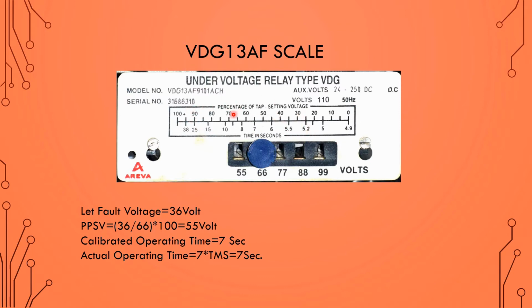And if you see the table, earlier in the case of over voltage it was PSM versus trip time, or PSM versus calibrated operating time, but here it is the percentage of tap setting voltage, or the percentage of this plug setting. So that means how much percentage of the plug setting you are giving, this shows that. 100% you are giving, 90% giving, 80% giving, 70% giving, or 0% giving, means 0 volt you are giving. So as you can see here, whenever we are reducing the percentage of the voltage, what is happening? The time to operate the relay is reducing. That means when we give 90%, it will give you 25 as the calibrated operating time, and similarly 20, less than 5.2 seconds.